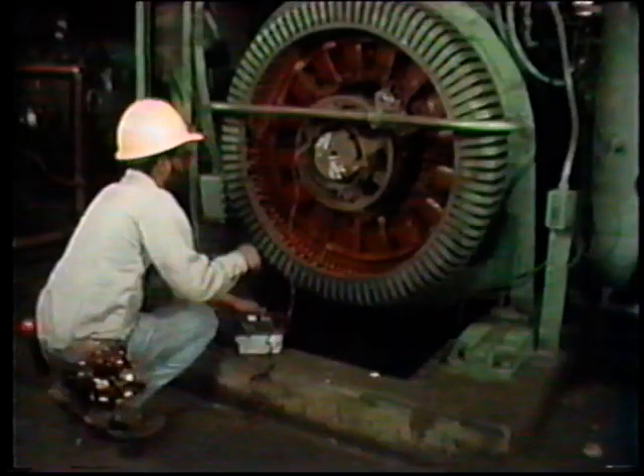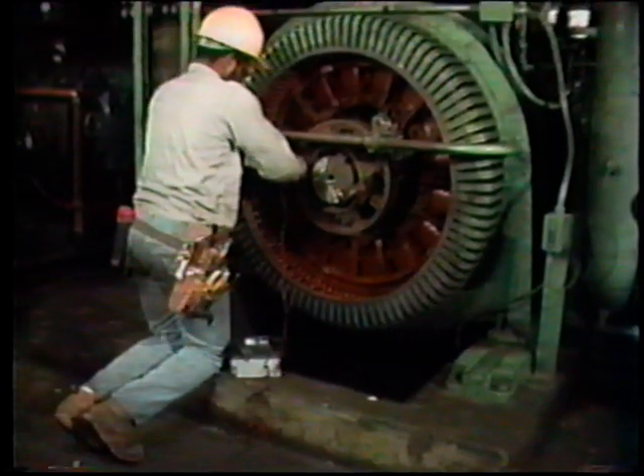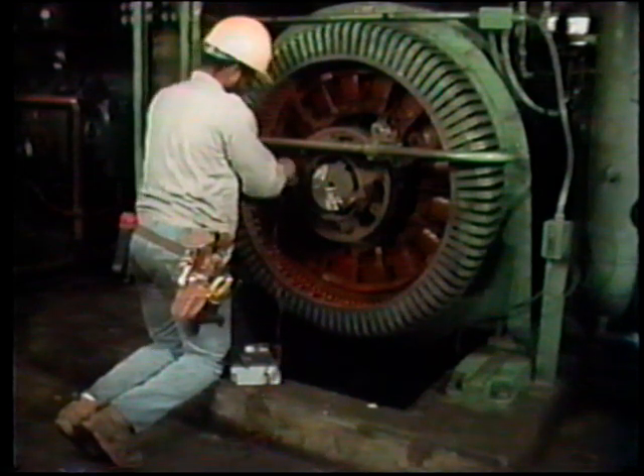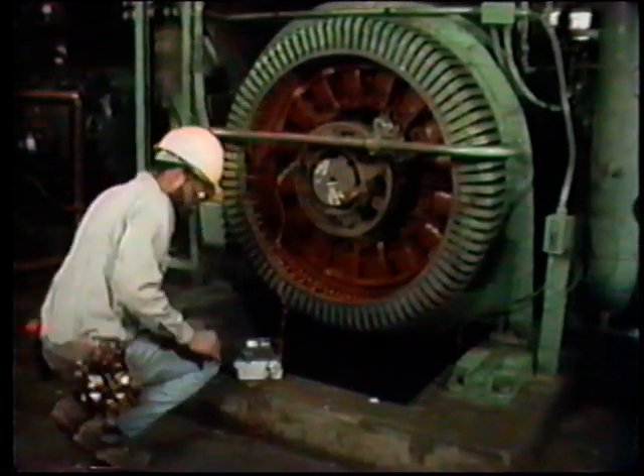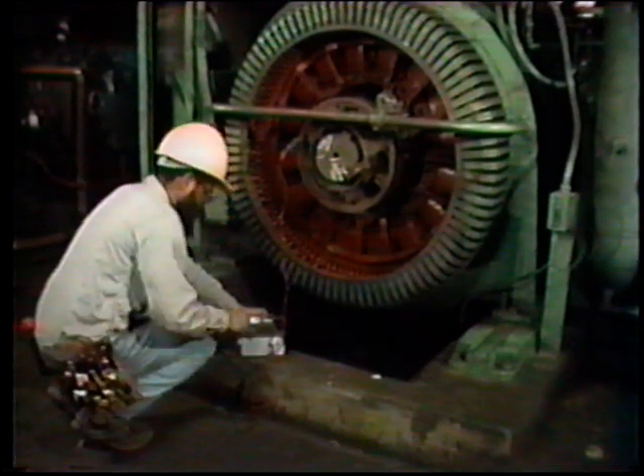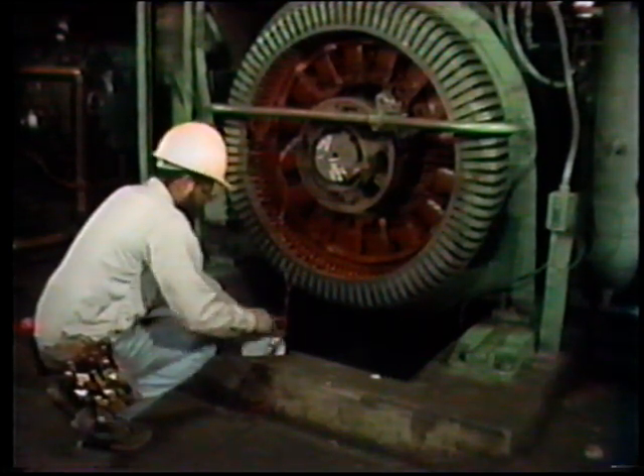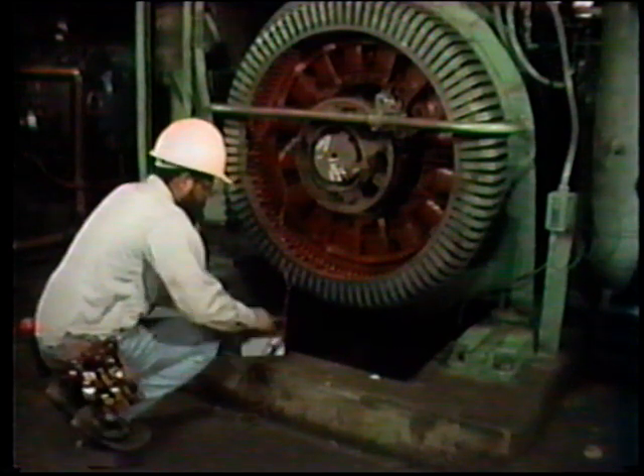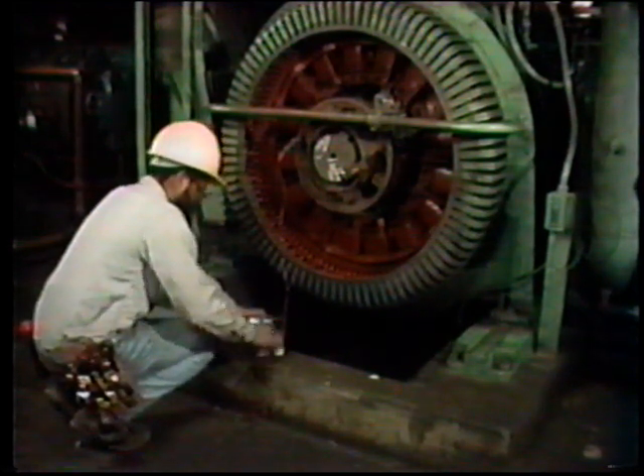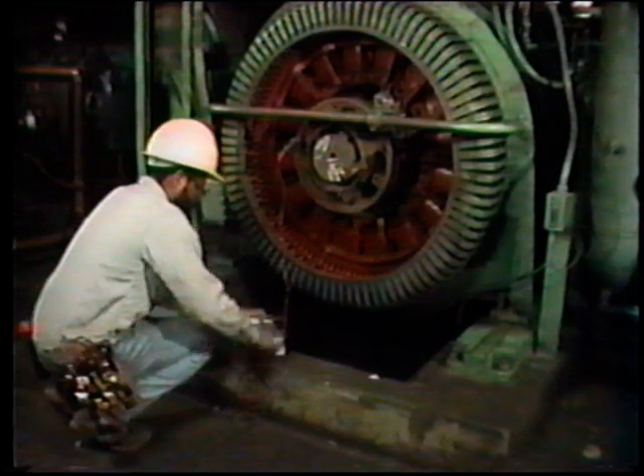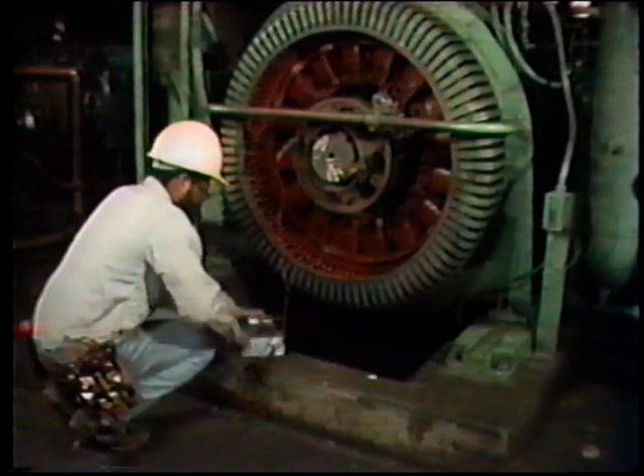The techniques for testing the stator and the rotor for grounds, opens, and shorts are basically the same. So for our purposes in this segment, we'll use the rotor of a synchronous motor to demonstrate the testing procedures for each problem. To test a rotor for grounds, use the same test procedures that we showed you earlier for testing rotor insulation. Remember, you use a megohm meter and test from one of the slip rings to ground. The megohm meter is operated for a period of time and a reading is taken. The reading is compared with previous readings taken under the same conditions to see if a trend is developing.